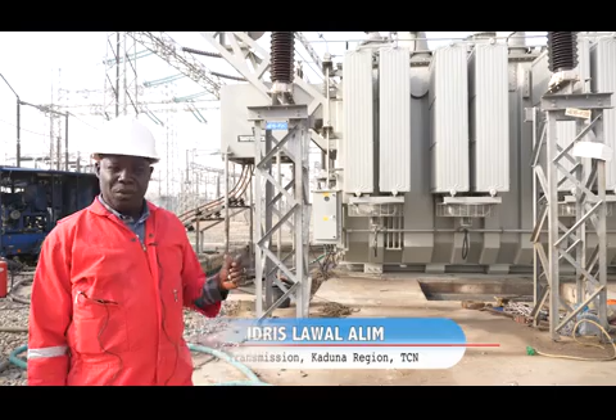That transformer is out. What necessitated us to start working on it is that when we carried out the test on T3A, we found out it has a problem with the winding, and as a result, we feel this transformer cannot come back online because of the winding problem — it has to go to the workshop. But for the one that got burned, when we opened the transformer, we found that a compartment, the tap changer compartment, was filled with water, and in fact the whole unit got rusted.